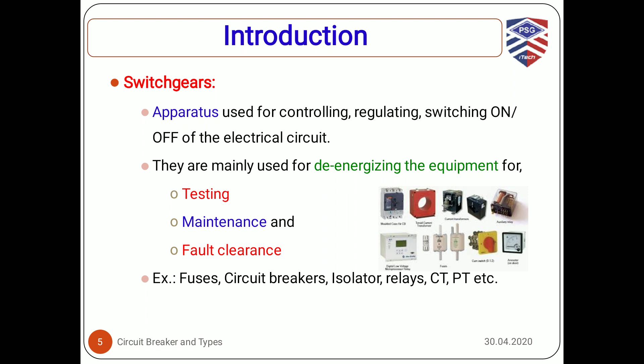Switchgear is not a simple or one component. All the components like fuses, circuit breakers, isolators, relays, and the current transformers, potential transformers, and so on will come under the switchgear category. And the protection system will consist of different blocks, different major components. It is categorized as sensing devices, relays, tripping circuit, and finally the circuit breaker. Any protection system will have all these four, out of which the tripping circuit is optional in some of the cases.